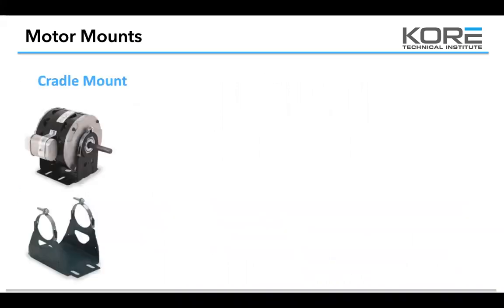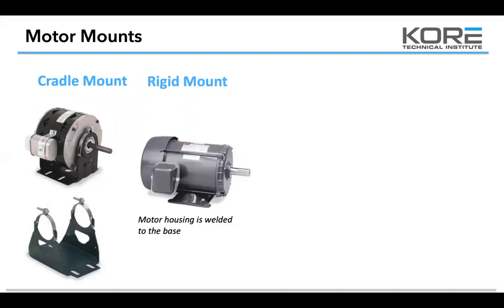So, motor mounts. You've got your cradle mount. Again, we see these all the time. Not my favorite. Usually those cradle mounts get loose, the motor comes off or wears out. That little rubber sleeve starts to wear down, and then the motor starts bouncing all over the place and wreaks havoc on whatever fan blade or blower wheel is on the end of it. The rigid mount's my personal favorite. Obviously, it's robust. It's usually on your larger motors, and it's able to handle whatever vibrations or situations it's running into, any harmonics, a lot better than the cradle mount.